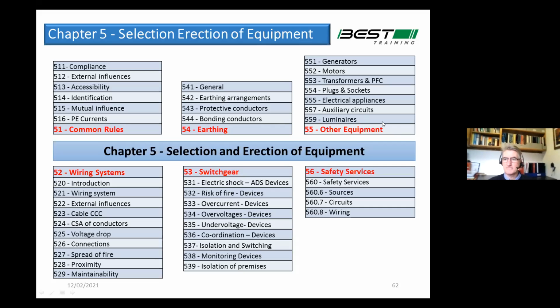But anyway, and then safety services, a very important chapter. Safety services is what we would have called in the past firefighter services. So firefighters lifts, evacuation lifts, smoke fans, all those types of things are covered in here. It also talks about emergency lighting and fire alarm and the essential power supplies to them. But really, I don't feel it should be there, because, you know, they're covered under standards, and the backup power supply is a battery within the system itself. So that's what's covered in that.